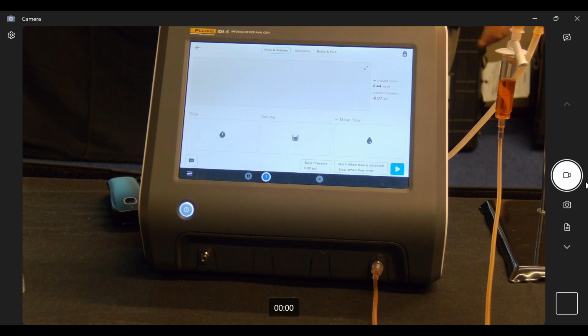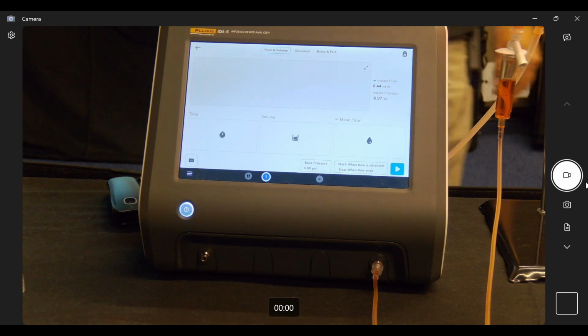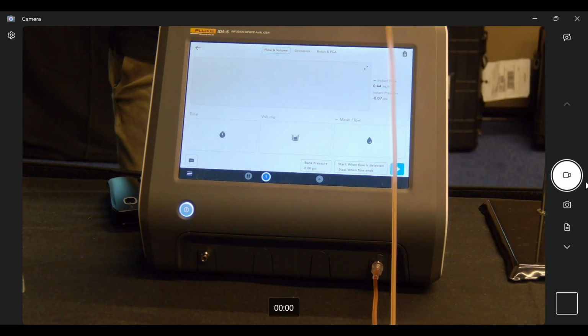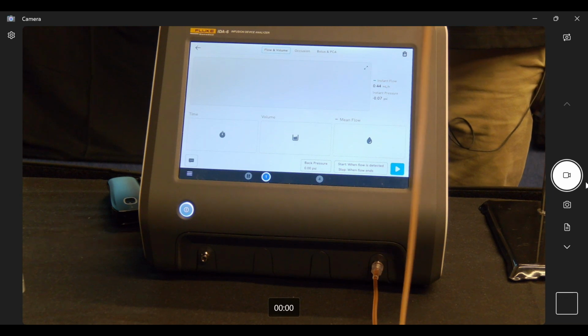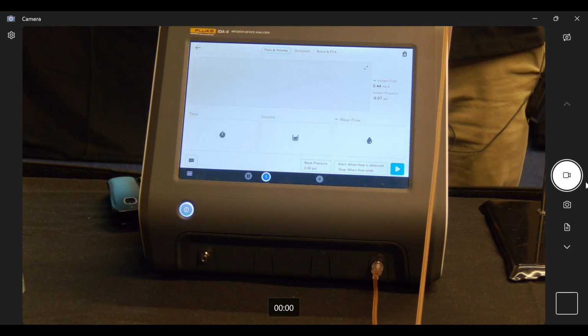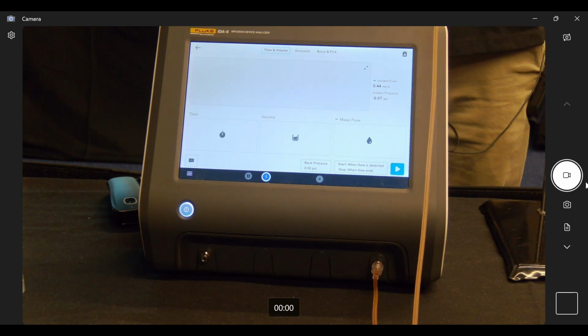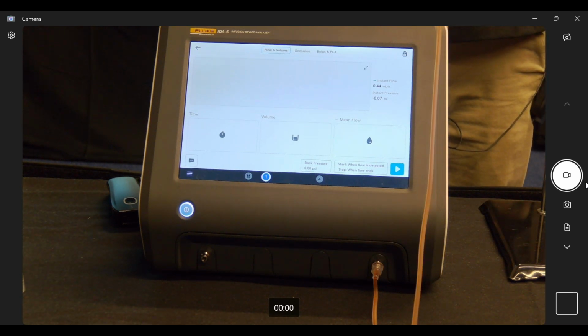As the fluid's coming up, it's recycling it back into the bag, which is a really cool trick. But what's even more impressive is we have static head pressure. When you read your service manual, Baxter guys, your head pressure is 24.5 inches, plus or minus 5 inches, from here to the head of the IV pump and your pressure meter. As your day goes and you're drawing this down, you're supposed to either raise your bag or refill it.